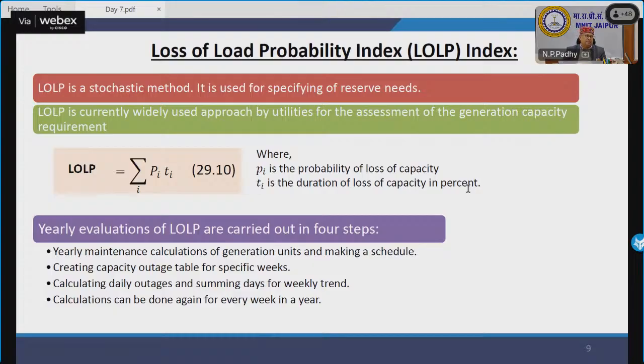But what is the minimum excess energy I must have so that I can manage is the question. If someone tells me you are catering 1 megawatt, you have 2 megawatt, 100% backup. But that will be more expensive, no? So I must optimize how my loss of load probability can be optimized. Yearly evaluation of LOLP is carried out in 4 steps. Yearly maintenance calculation of generation units and making a schedule, creating capacity outage table for specific weeks, calculating daily outages and summing days for weekly trend. Calculation can be done again for every week in a year too. Are you clear? So this is how LOLP can be calculated.